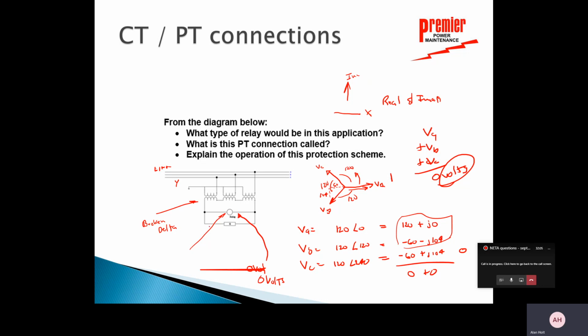So basically, the type of relay I want in this situation is a 59. It's an overvoltage relay. For a phase to ground fault, that voltage will go to 0 and I'll pick up a voltage here. So I want a relay that's going to see that overvoltage and give me an alarm or a trip. Okay. So basically, this scenario lets me verify or find a fault because of the unbalanced voltages.